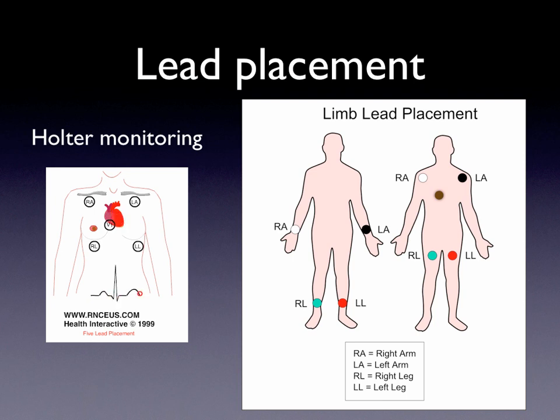For stress testing, the placement of V1 through V6 chest electrodes is the same as for a 12-lead EKG. However, the limb leads are placed up on the thorax itself so that the patient can move and walk appropriately. If the leg electrodes were actually on the legs while the patient is walking, that would produce a wandering baseline and significant somatic or muscle motion interference.